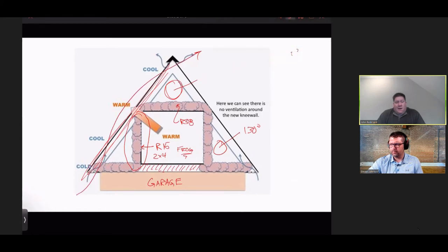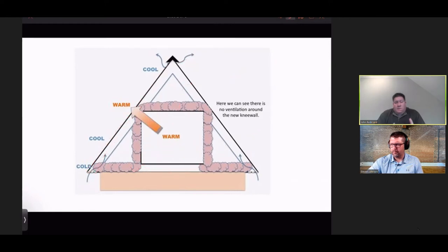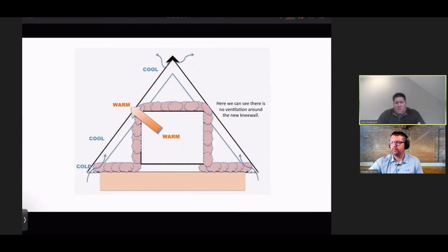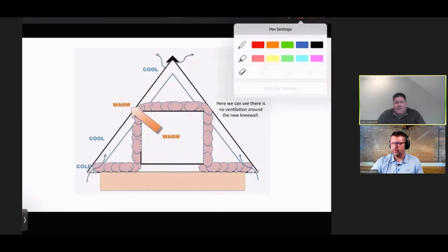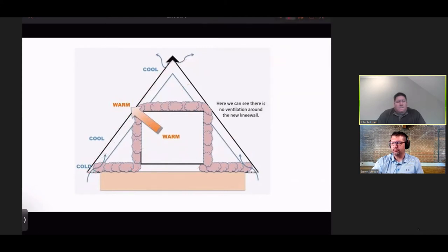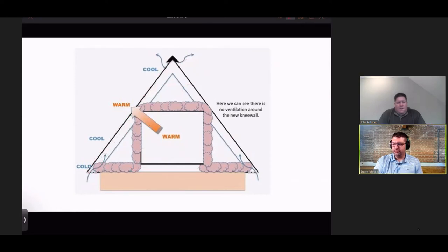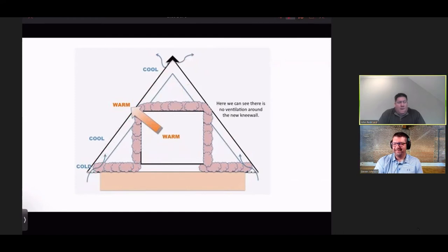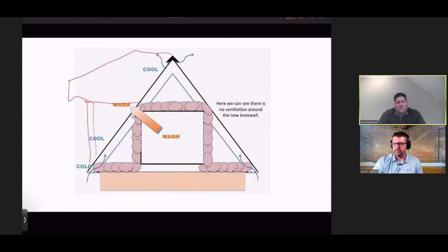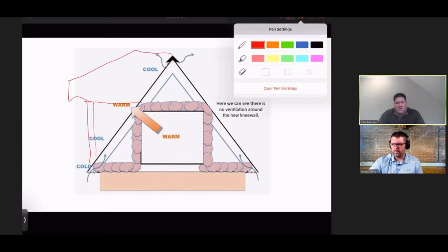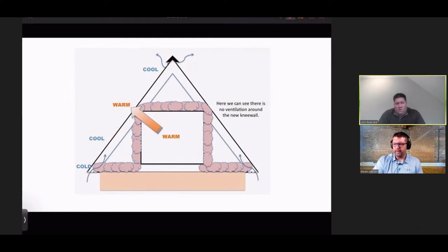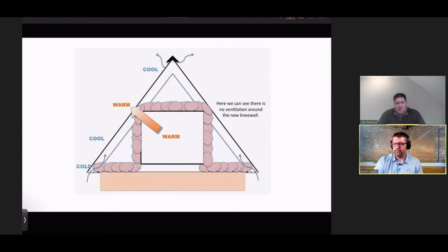You've also got airflow occurring. If you see in this photo, you've got insulation coming from the bottom roof line on the left, over to the right, up, and back over to the far right. That insulation coming down off the bottom of those knee walls is meant to block the airflow running up under that particular room. This is a common situation, this is what 90% of your bonus rooms look like.